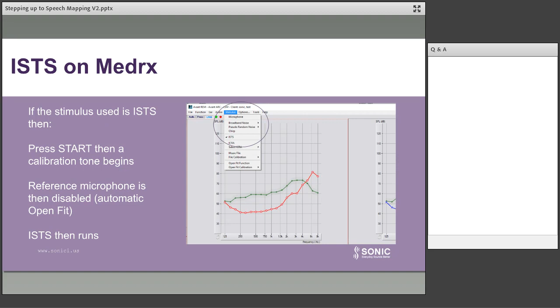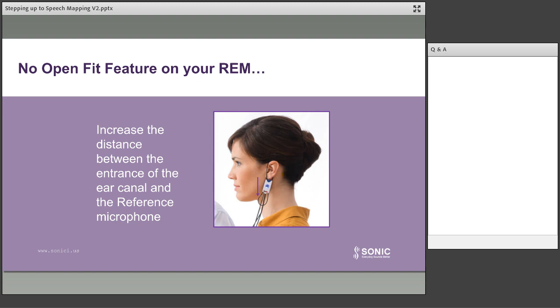That's pretty cool. Now, you might unfortunately have older equipment that doesn't have an open fit feature in it. So at least you should be pulling the reference microphone further away from the opening of the ear canal, so there's less chance of any sound that's leaking out getting back into that reference microphone.